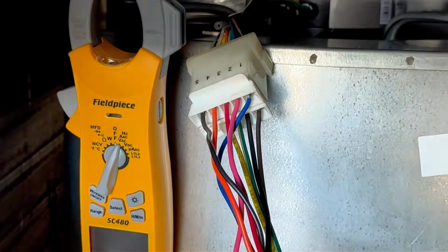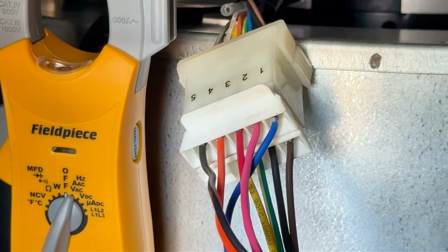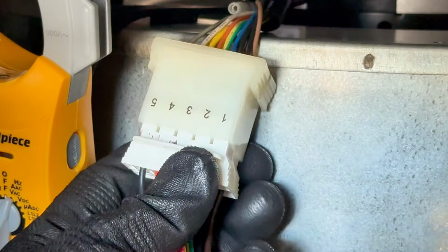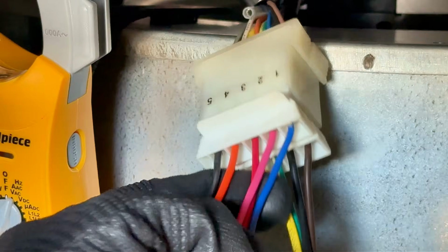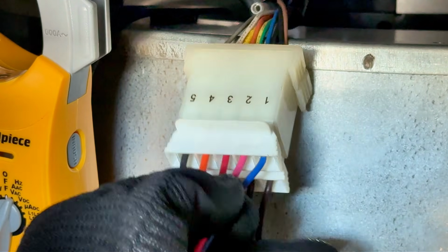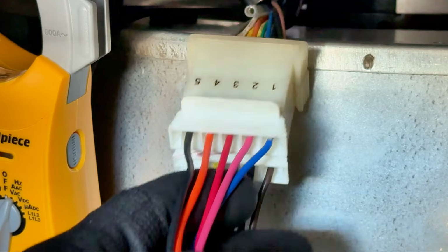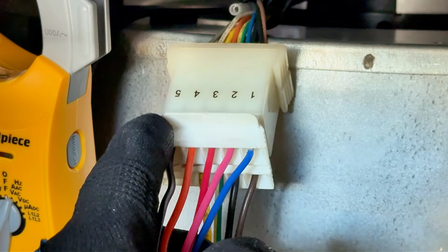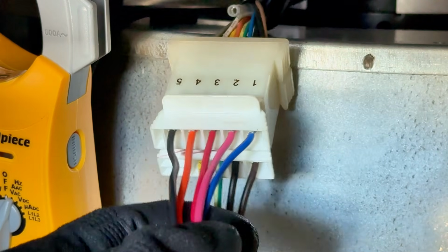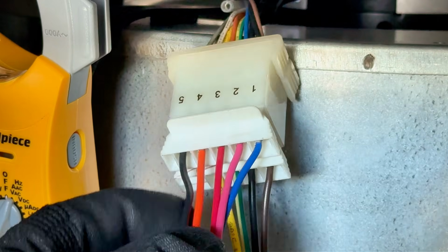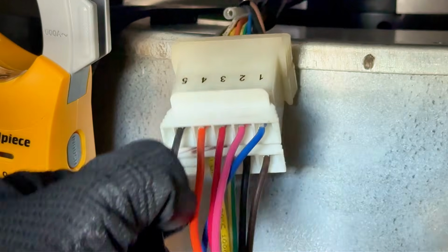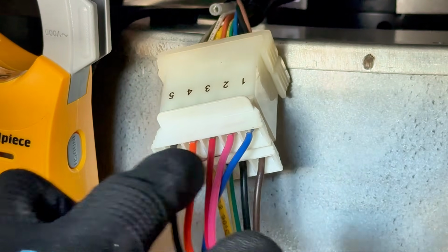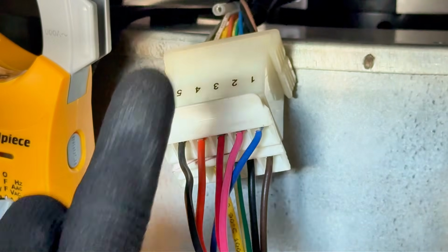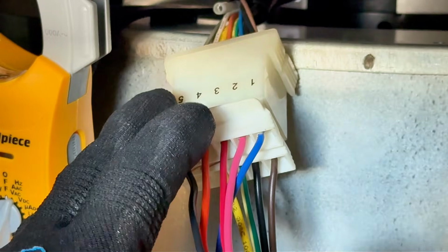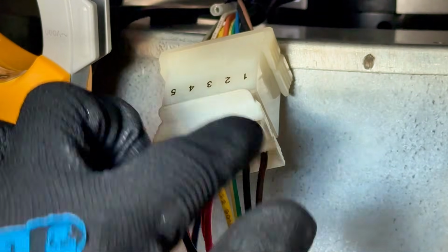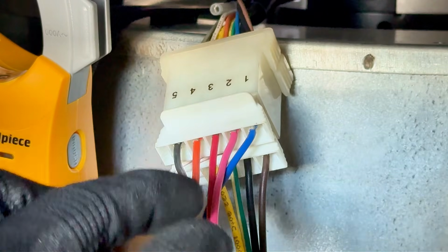So a couple of things to kind of just make sense of here. You got a bunch of wires, right? But if you look on the top, you got numbers 1, 2, 3, 4, 5. So on top, you got 5 wires, 5 speeds. These top 5 only receive 24 volts. And number 1 is the slowest speed. Number 5 is the fastest speed. So in this specific package unit, the way it's wired, when we call for cooling or heating, we send 24 volts on this one here. But you can always change the speed if you want to. So one test is going to be checking for low voltage. With an ECM, you also have high voltage present. So top is only low voltage and only one can get 24 volts at a time.